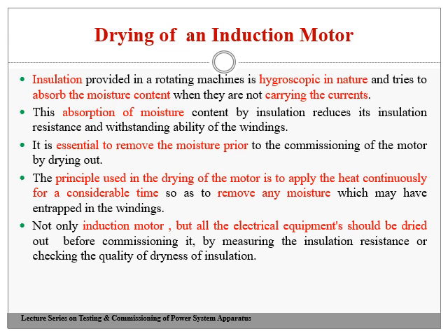Now, let us go with the drying of an induction motor. As you already know the meaning of drying in the case of the transformer, in a similar fashion here also, the insulation provided in the rotating machine has a property of absorbing moisture content. That's why we call it hygroscopic in nature, and it tries to absorb moisture when it is not carrying current. Suppose I keep the induction motor without installation, at that time moisture may enter the insulating medium provided in the induction motor. It is going to happen when we keep the induction motor without allowing current flow to it, or not in operating condition.